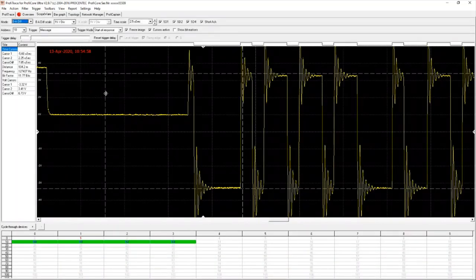The vertical cursors are used primarily to identify distance to a specific fault. In my training setup with cables less than 4 meters long it won't give much accuracy, but in a plant with a 100 or 200 meter segment, connecting the first cursor and second cursor to the point where the problem starts — whether it's a short circuit, wiring error, impedance mismatch from incorrect terminations, or incorrect device — can give an indication of how far away from where you're connected that problem is.